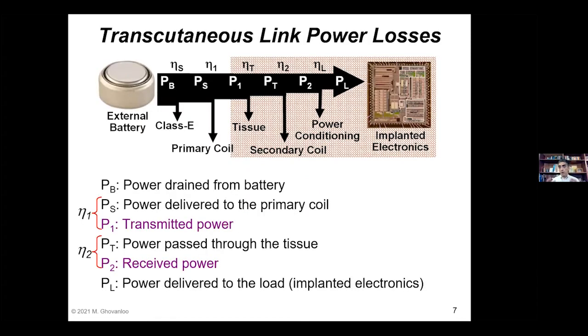So fundamentally, from the system level point of view, you have the energy source, basically the battery, sometimes a replaceable battery. For example, these cochlear implants have this behind-the-ear processor where you can either recharge or replace the batteries, almost similar to a hearing aid. So the energy source is outside of the body, and then your electronics, the target where you want to power, is inside the body, and you want to deliver power from the energy source to your electronics.